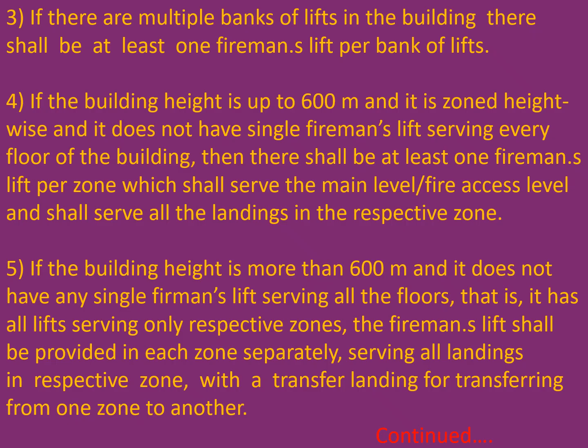Friends, we are talking of the fireman lift. The third, if there are multiple banks of lifts in the building, there shall be at least one fireman lift per bank of the lift. Fourth provision, if the building height is up to 600 meter, and it is zoned height wise and it does not have a single fireman lift serving every floor of the building, then there shall be at least one fireman's lift per zone which shall serve the main level, fire access level, and shall serve all the landings in the respective zone.